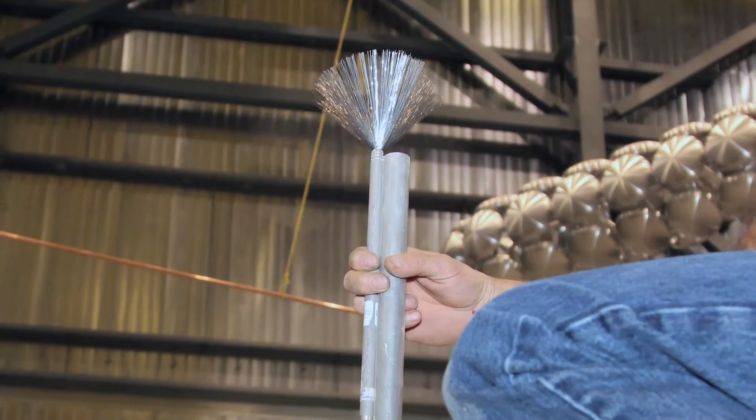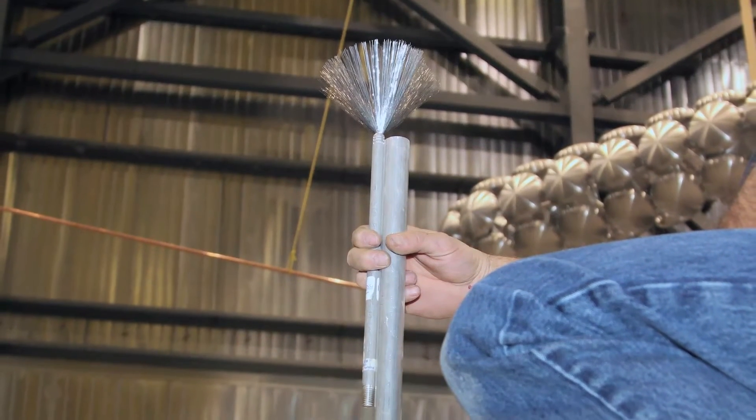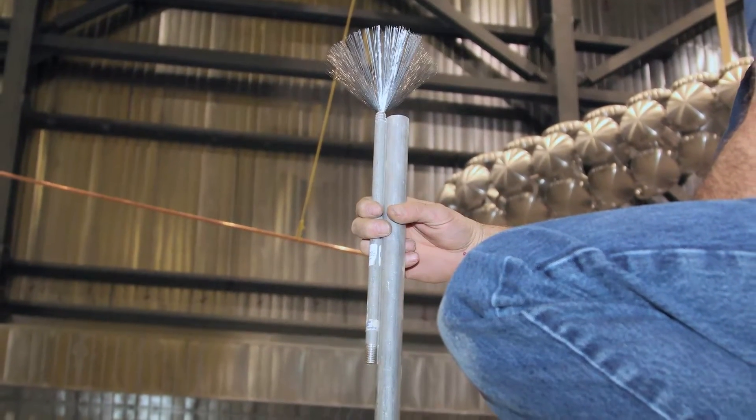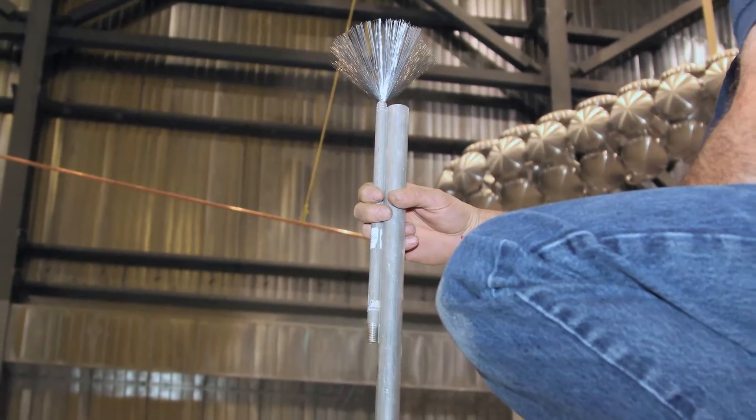A commercially available static dissipator is bonded to the grounded center pipe on the outside of the tank. Sparking continued to appear on that same center pipe on the inside of the tank down to an applied voltage of 350 kilovolts.